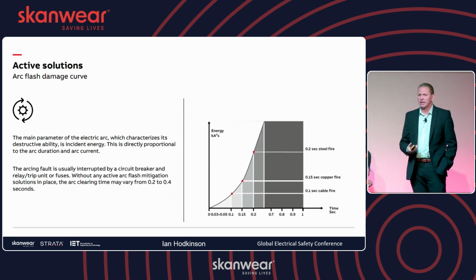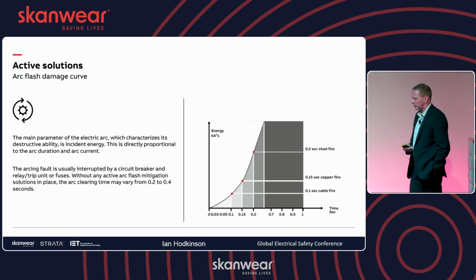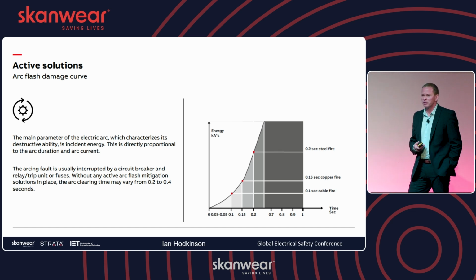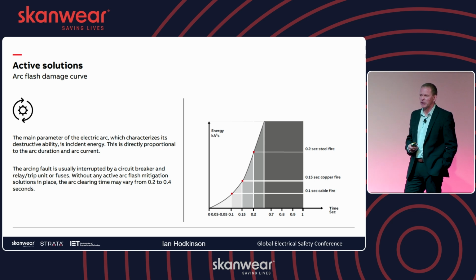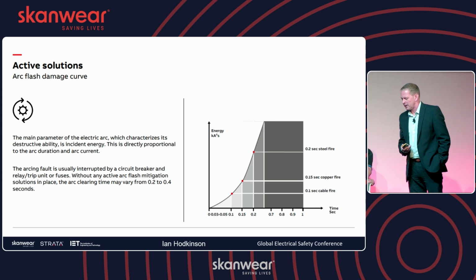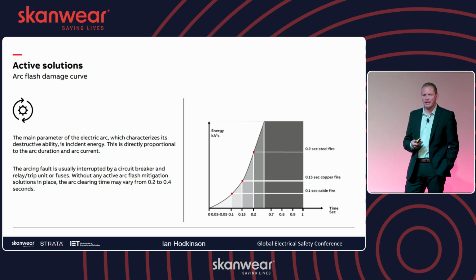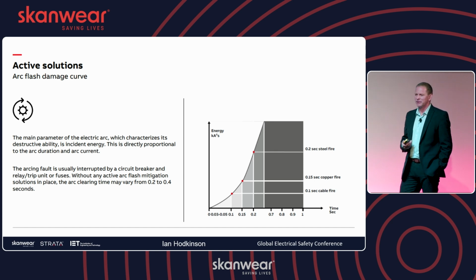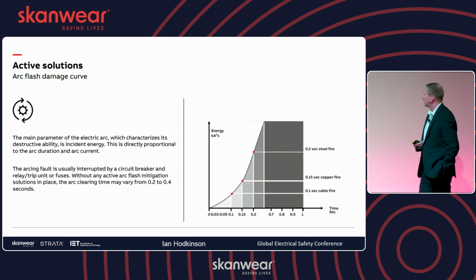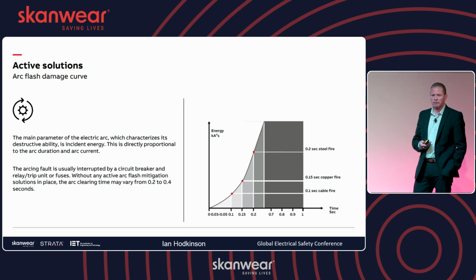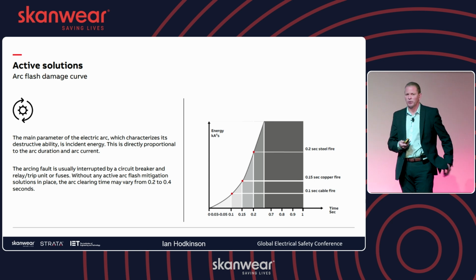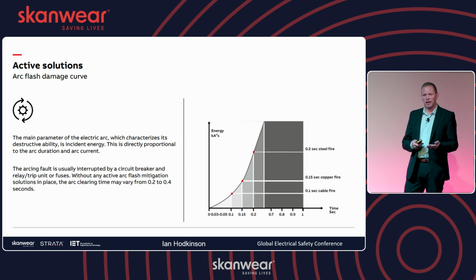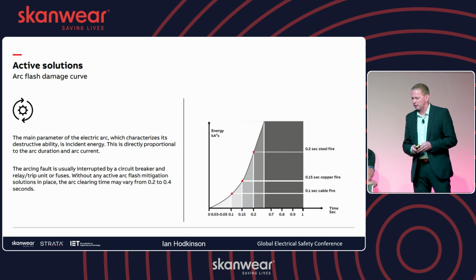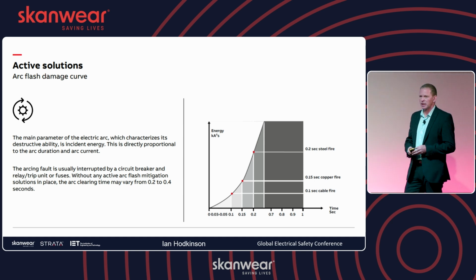Then we move on to active protection in our portfolio. Like Mikko demonstrated well, you see the energy surge up, but the thing that hits first and foremost is the light, because light is the fastest speed, as we always say. If you can detect the light, you'll detect it very early, which enables you to act. Once you've detected the arc, you can employ the protection, and the important thing is to get the clearance time as quick as possible. The lower you get that time, the less energy you're exposing the board and personnel to, and the less risk of damaging your assets. These are the key points already mentioned this morning: safety for personnel, safety for your assets, and keeping the lights on.